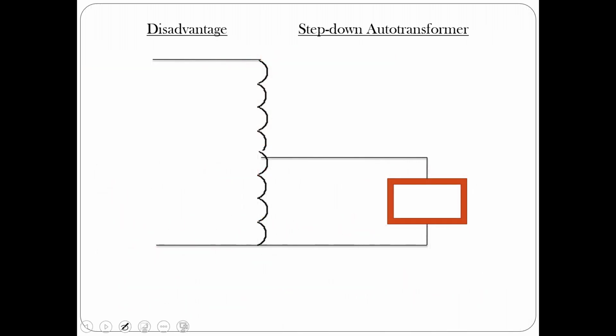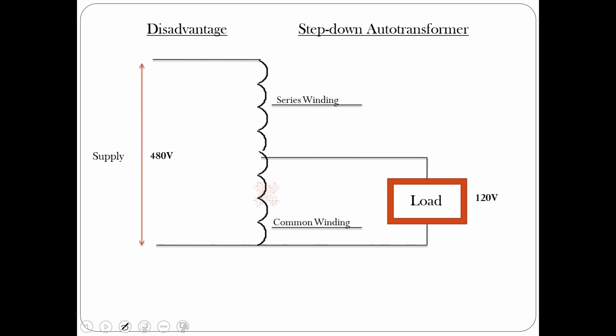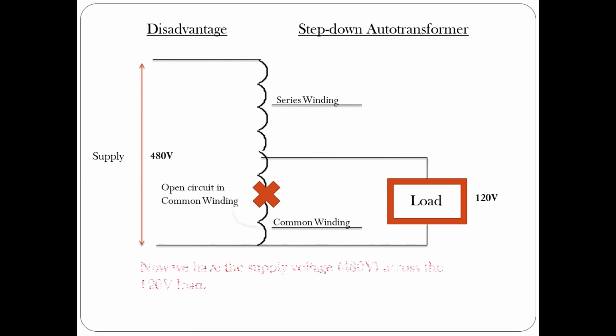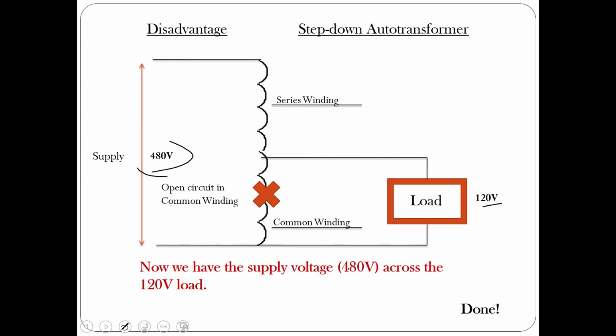I've got a little diagram of what that fault might look like. We're trucking along here, and we've got your series winding, your common winding, and a 120 volt load and a 480 volt supply. All of a sudden, whammo, for some reason we get an open on this common right here. The common opens up. If that happens, we could see as much as 480 volts across our 120 volt load over here. So that voltage could rise to just about the supply voltage. That could be quite hazardous for the load, and could make it burn up.